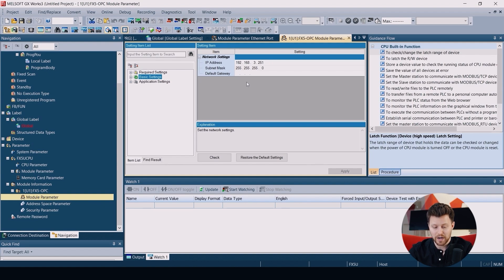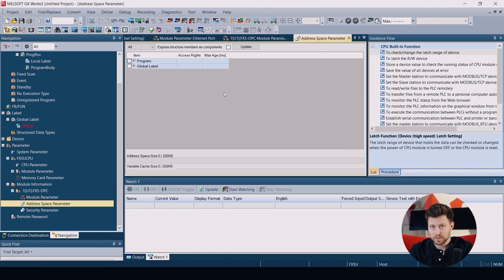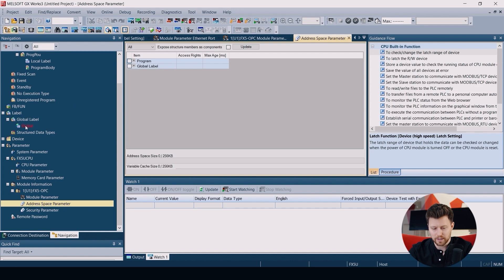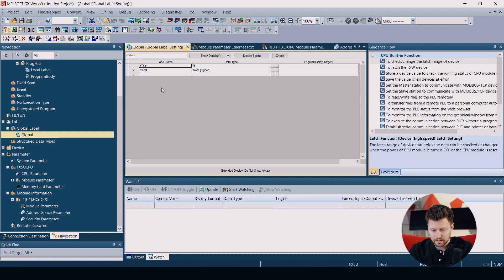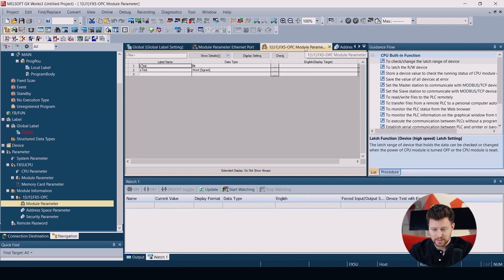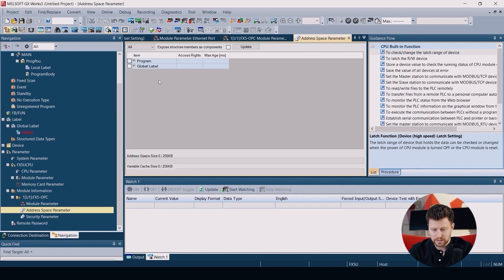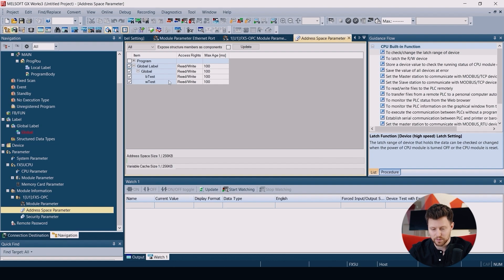Then we can go to address space parameter. Here we will choose which variables should be available in our OPC UA communication. So I already prepared two variables. So when we go to label and global label, you will find two variables that I already have in my project. So let's go back to the address space parameter. And as you can see, these values are also available here. So let's check them and make them available for our clients.